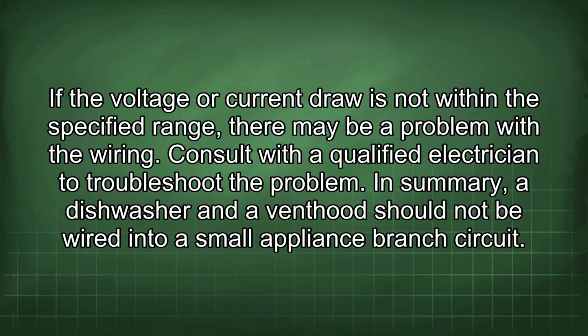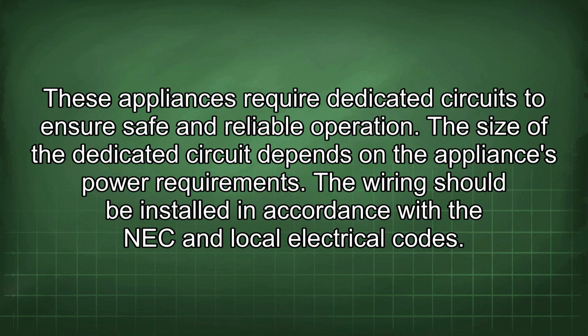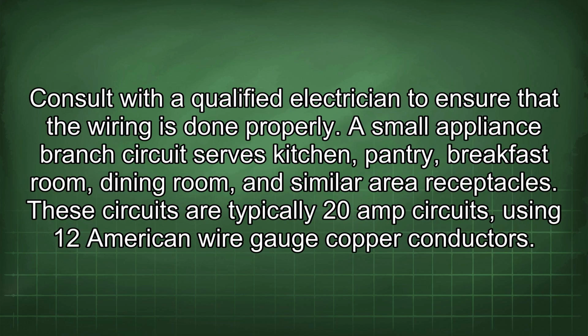In summary, a dishwasher and a venthood should not be wired into a small appliance branch circuit. These appliances require dedicated circuits to ensure safe and reliable operation. The size of the dedicated circuit depends on the appliance's power requirements. The wiring should be installed in accordance with the NEC and local electrical codes. Consult with a qualified electrician to ensure that the wiring is done properly.